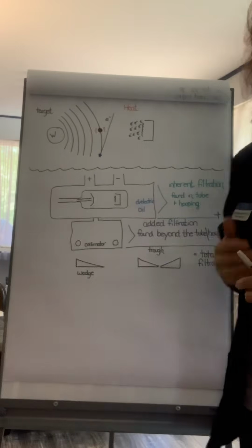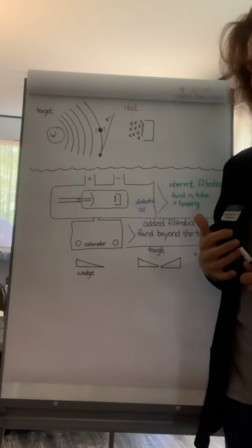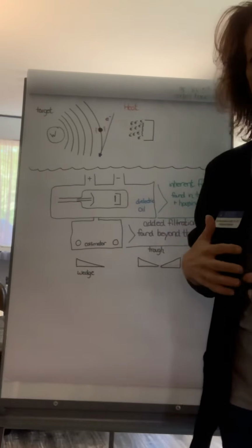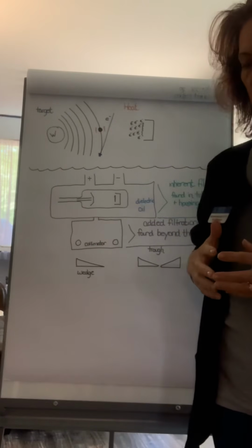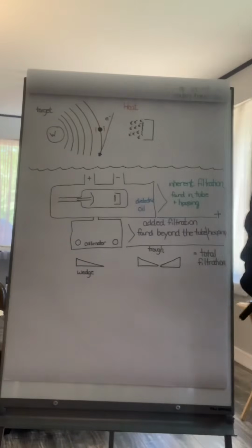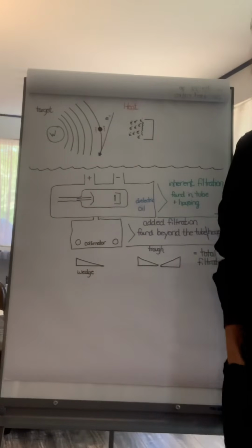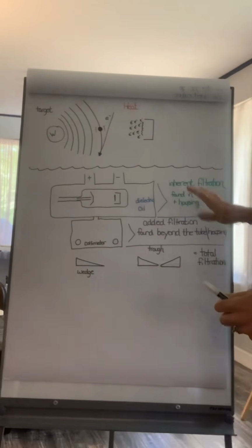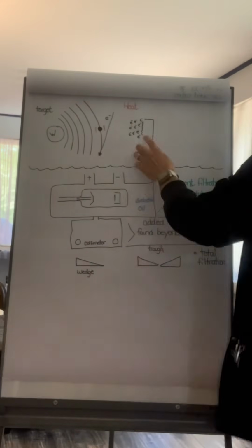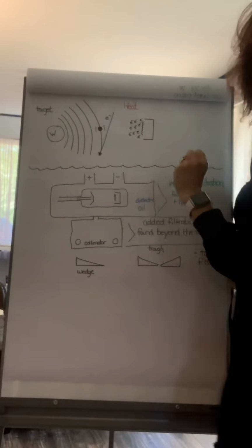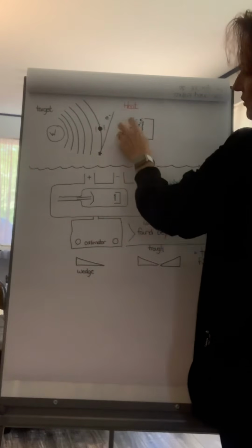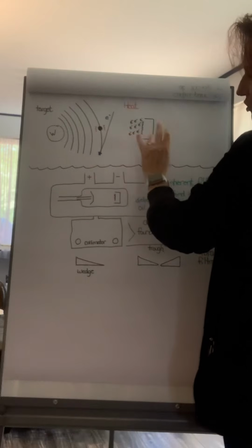So they tell us that 99% of what takes place in the actual tube is heat. Remember, that's 99% of a ridiculously large number. So when we're talking about that 99%, you're talking about millions of billions of electrons that have the potential to bombard that target. So what happens, you've got the focusing cup over here made of nickel, you've got the filament that's thorium and tungsten, and then you've got your electron cloud or your space charge right here.